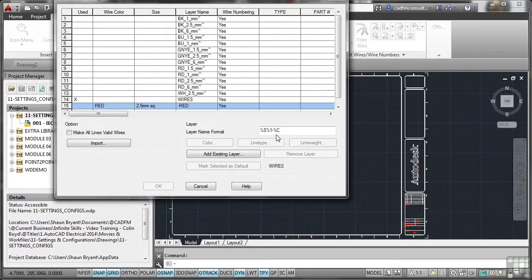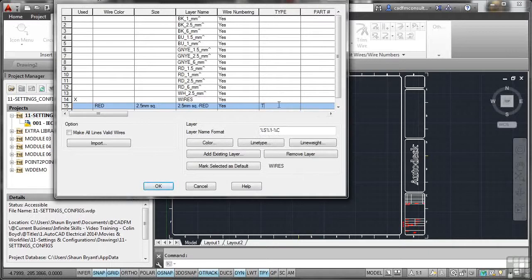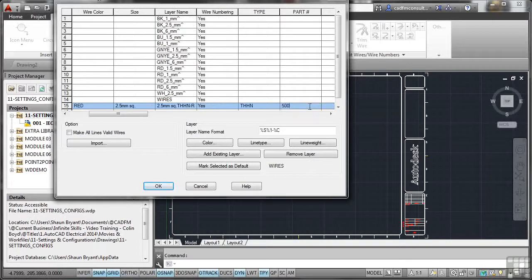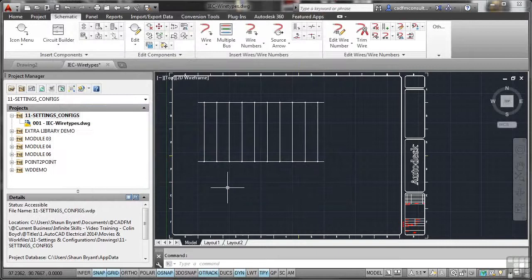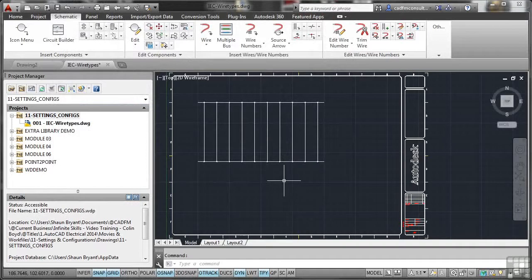Notice as you set these values, you'll see the layer name follow that convention — all layer names follow the layer name format. S is size, C is colour. Also notice there are our user columns: type and part number. I'm going to change type to THHN — just something pulled from the hat — and part number will be 500. Check the layer name format and make sure it's %S, %1, dash, %C. You can see it's putting all that information into the new layer name. Once you've put all that information in, click OK. That has defined a new smart layer for your wire numbering.